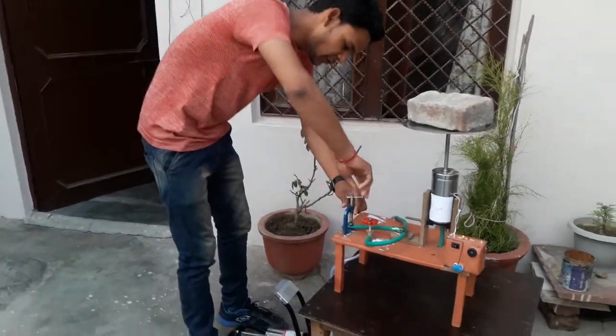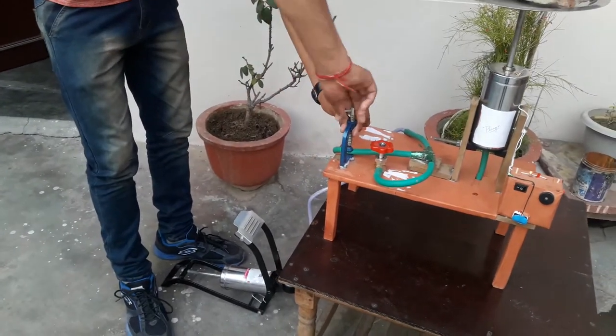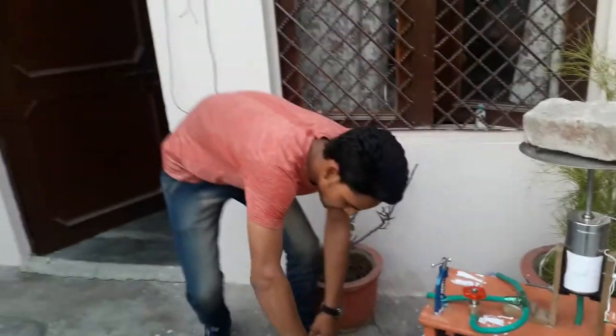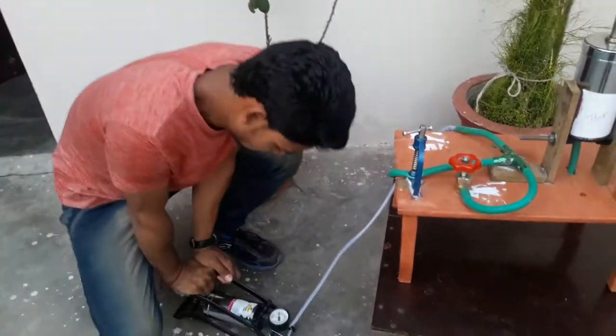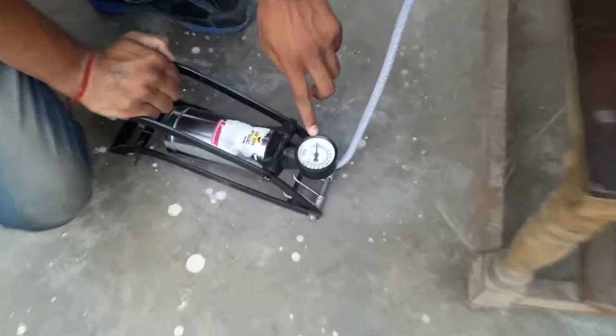Now we want to show how much pressure the valve reads while it lifts. I am going to close the C clamp and through that the pressure valve. I think it is about 15 bar.